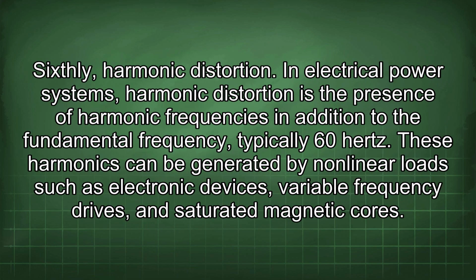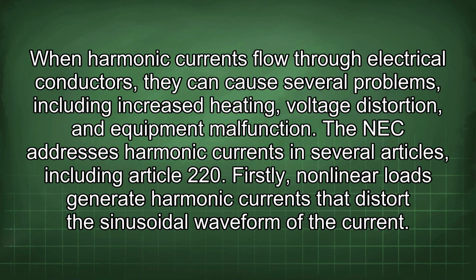Sixthly, harmonic distortion. In electrical power systems, harmonic distortion is the presence of harmonic frequencies in addition to the fundamental frequency, typically 60 Hz. These harmonics can be generated by nonlinear loads such as electronic devices, variable frequency drives, and saturated magnetic cores. When harmonic currents flow through electrical conductors, they can cause several problems, including increased heating, voltage distortion, and equipment malfunction. The NEC addresses harmonic currents in several articles, including Article 220.